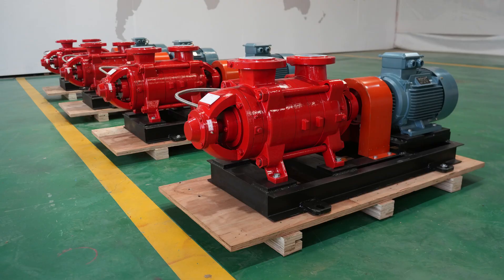Then the boost phase — that's where the pressure builds. The impeller spinning super fast gives the water kinetic energy, boosting its pressure way up, high enough to get into the boiler against the pressure already in there. You have to overcome that. For really high-pressure jobs you get multi-stage pumps — multiple impellers, one after the other on the same shaft. Each one adds more pressure, like extra engines on a rocket giving it more thrust. Finally, the pump forces that high-pressure water straight into the boiler drum, where it gets heated and makes steam.